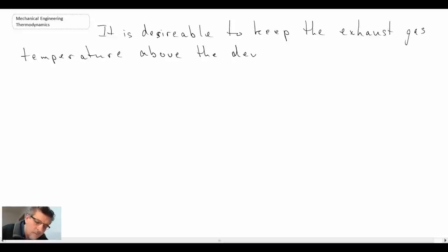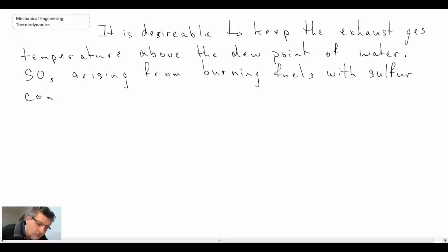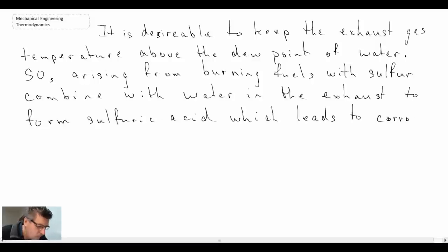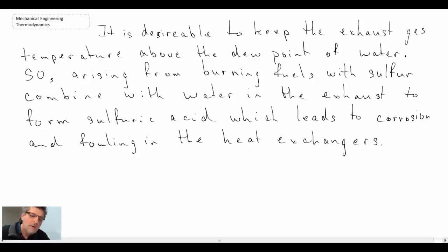So I'm just going to make a couple of comments here about the operation of boilers that we need to be a little careful with, because you can have byproducts of combustion that can cause damage to your boilers. Depending on what you're burning as the fuel in your boiler, sometimes there can be trace elements of sulfur, especially if you're burning coal. And that sulfur, through the combustion process, can generate different oxide compounds.